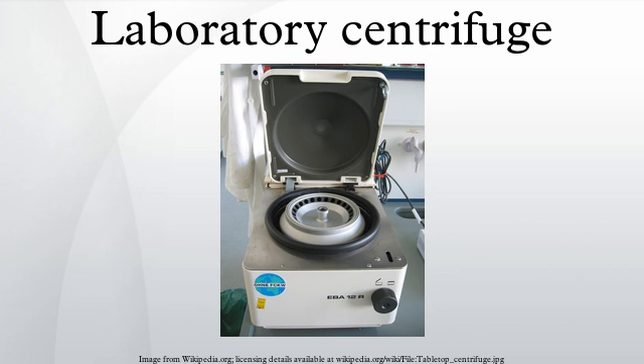Larger samples are spun using centrifuge bottles, which range in capacity from 250 to 1,000 ml. Although some are made of heavy glass, centrifuge bottles are usually made of shatterproof plastic such as polypropylene or polycarbonate. Sealing closures may be used for added leak-proof assurance.